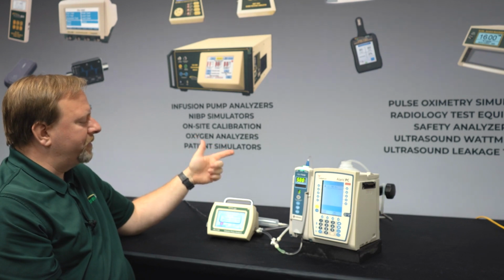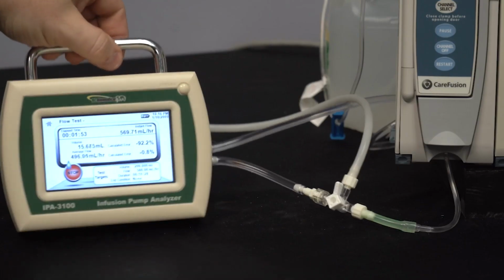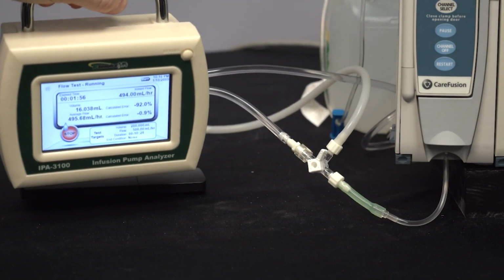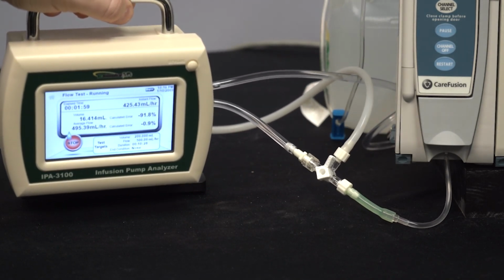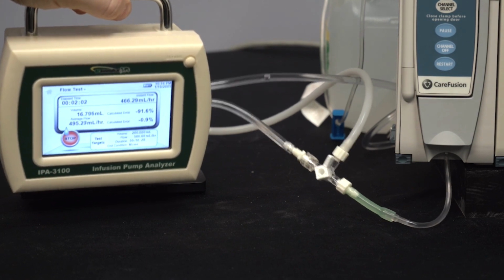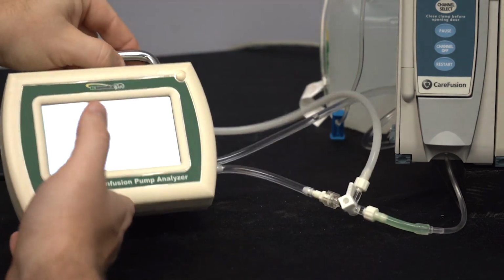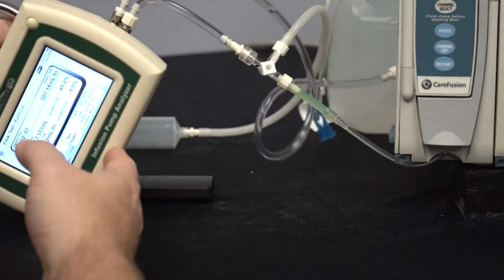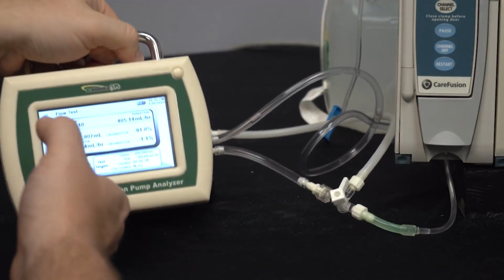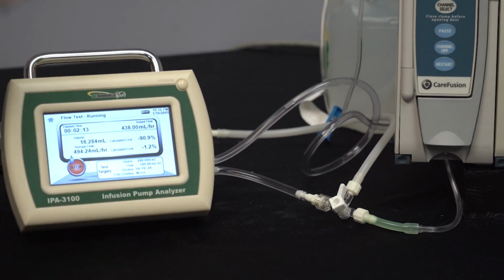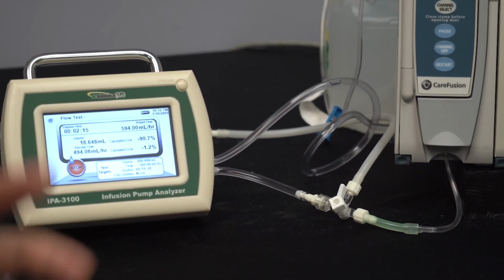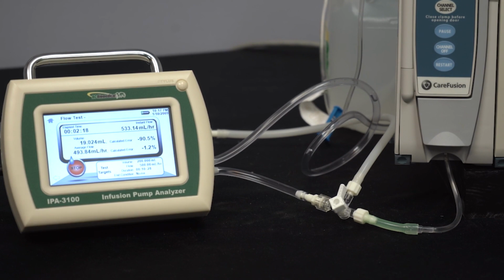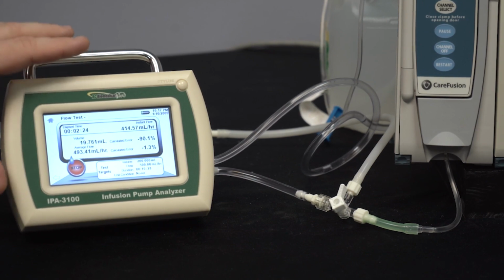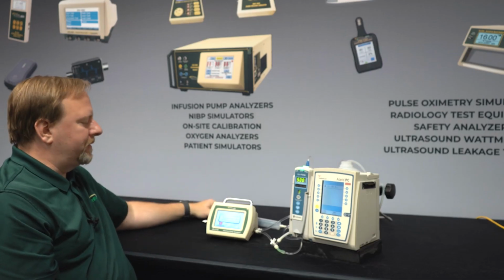Another thing we can demonstrate here is that it really doesn't matter how I have the IPA 3100 oriented. Whether I'm doing a low flow test or a high flow test, I can hang this from an IV pole, I can set it on my desk, I can put it on its side, I can have this unit anywhere that I need to, that it'll fit in my luxurious workspace, and it really doesn't affect anything. So that's another benefit of this system: the orientation of the analyzer doesn't affect the readings or the measurements, regardless of what flow rate we're running.